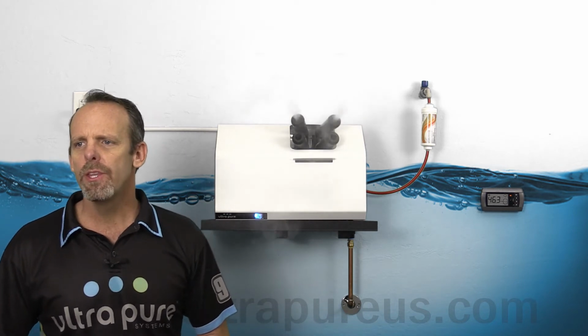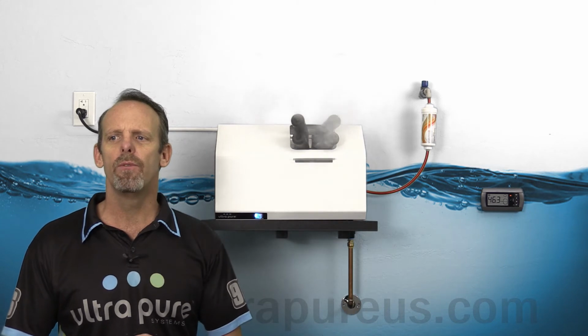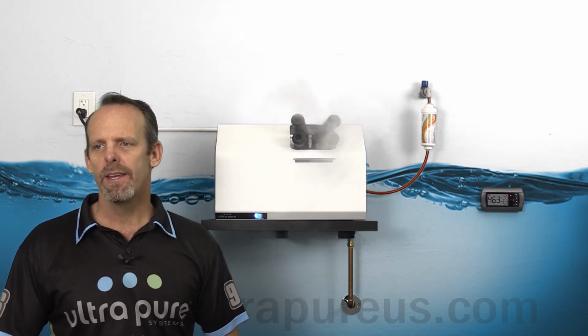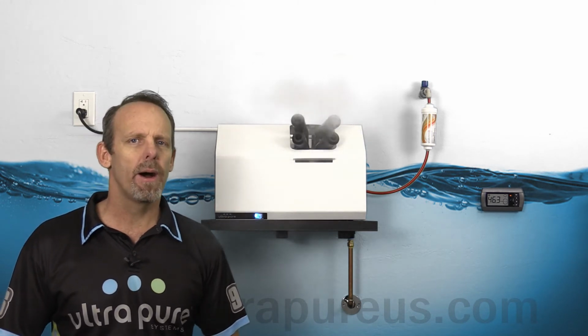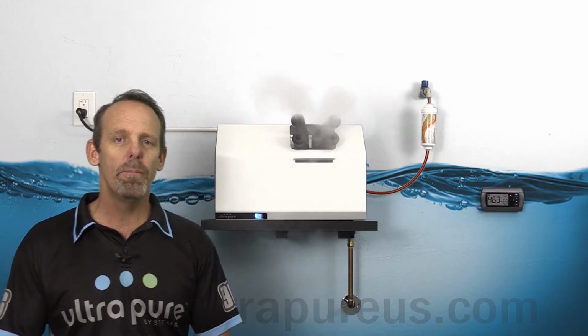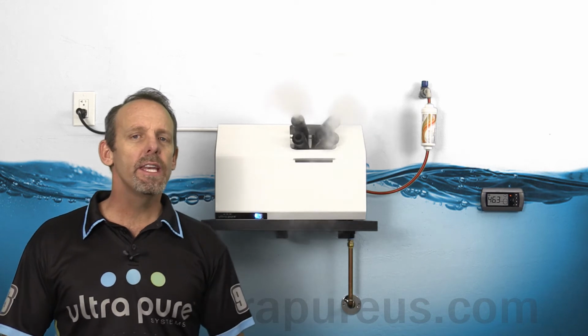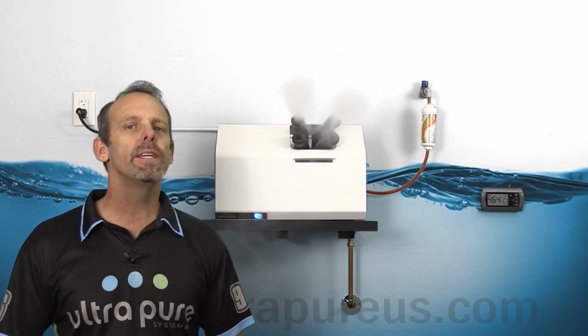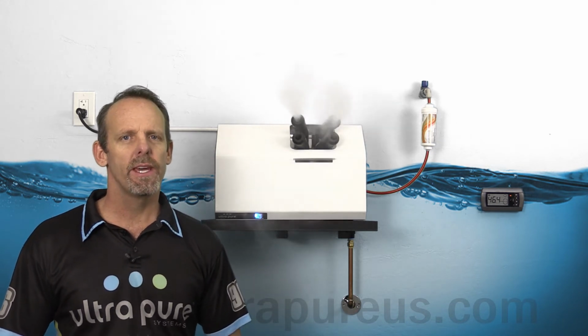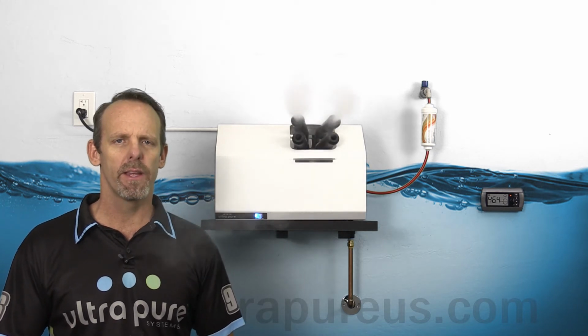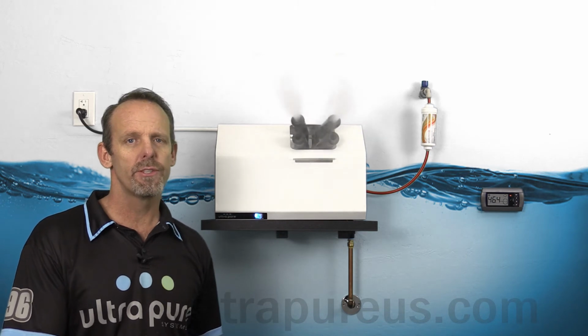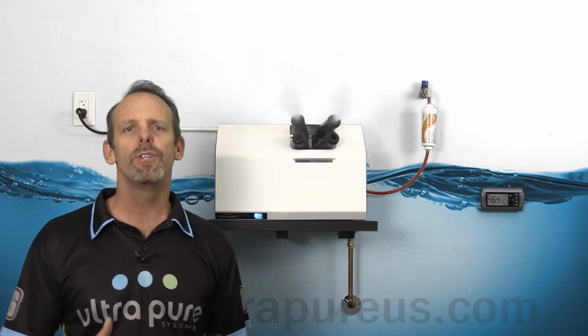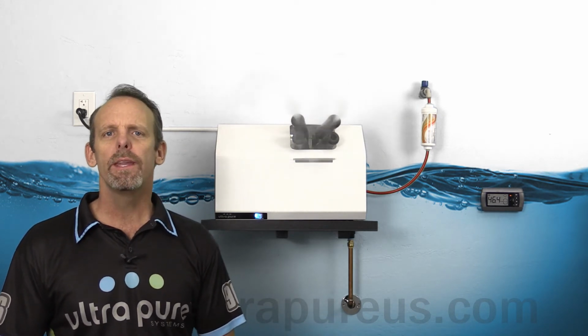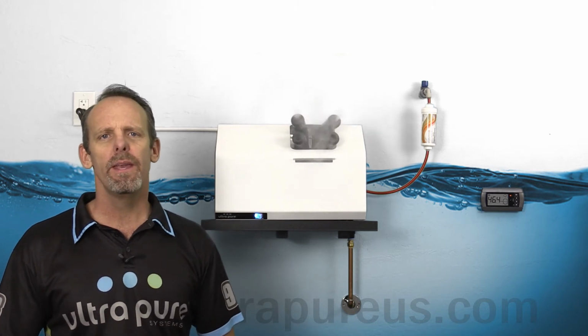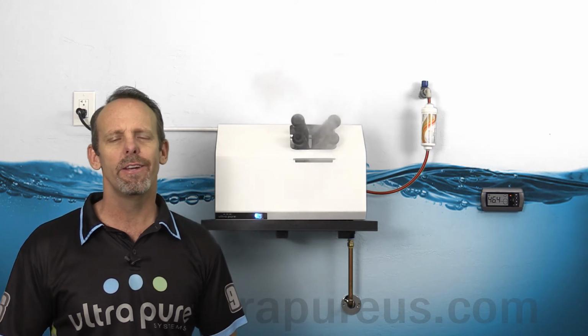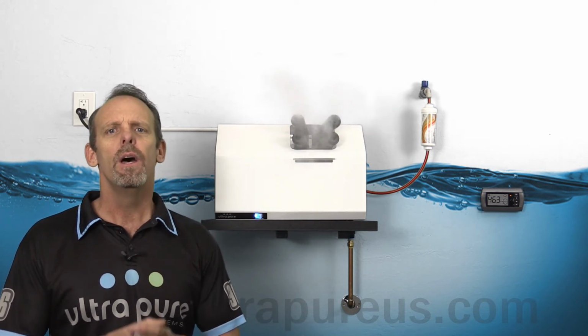The first question: can you use dew point control with the Sigma line of wall-mounted humidifiers? It comes from Jose in Las Vegas. To answer your question today, that is not possible. We do not have that option on our line of humidifiers, but the manufacturer of these humidifiers, out of Italy, is definitely developing and actively looking into adding dew point control. It's an engineering practice that needs to be developed, because we already have the temperature sensors and humidity sensors on board. Now the software just needs to be written so we can calculate dew point, and at that point we can control off of it. I'm hoping by mid-year, depending on what happens internationally, but we'll just have to see — it's definitely in the works.